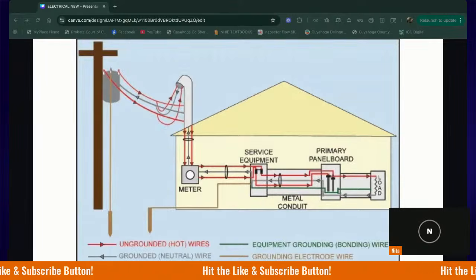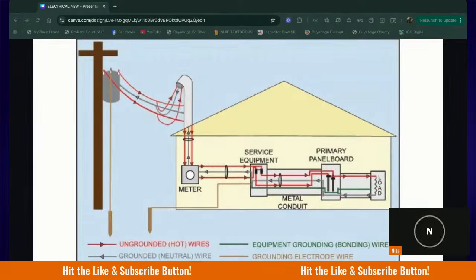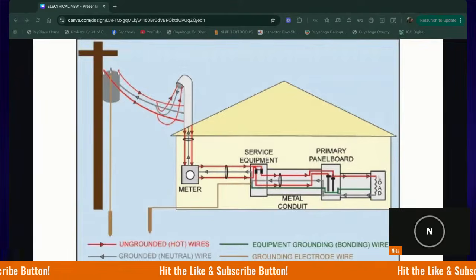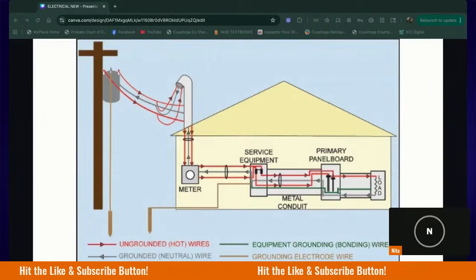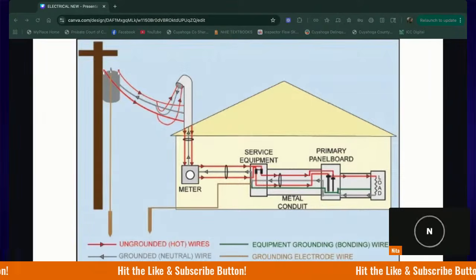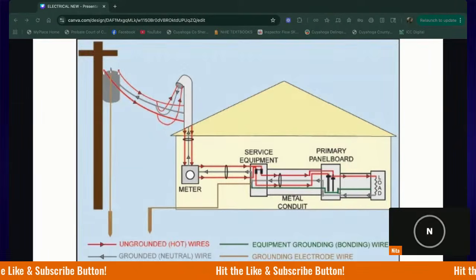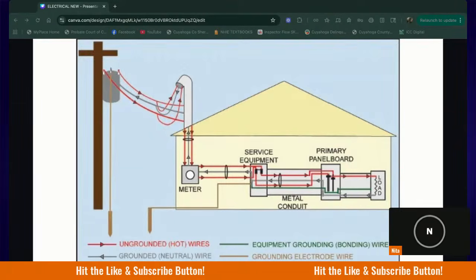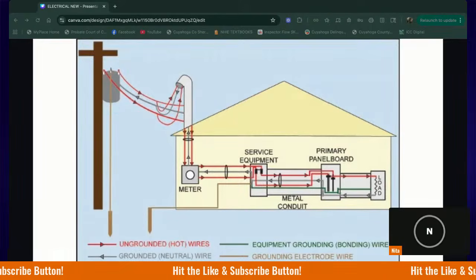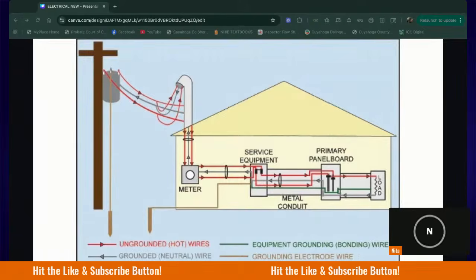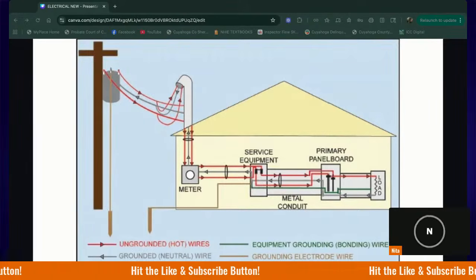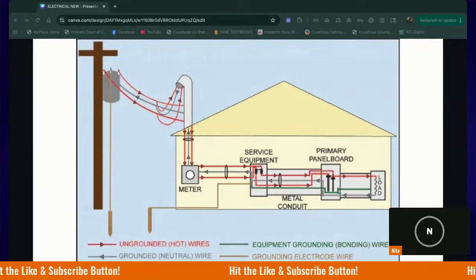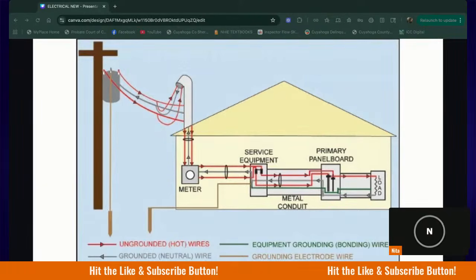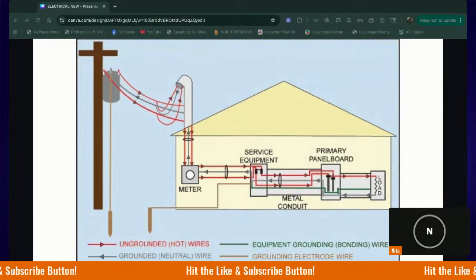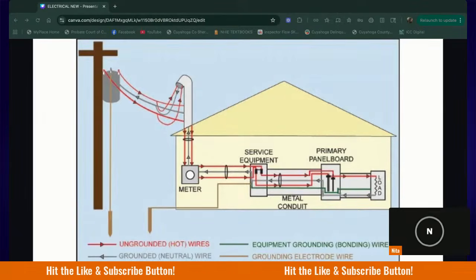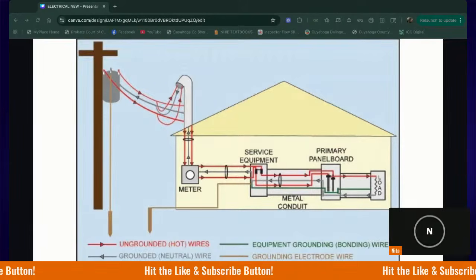Each load or each thing that we are trying to power has what's called an equipment grounding conductor or an EGC. This is the safety wire. Okay, so it is not intended to carry current. When everything is working correctly, this green wire here is not intended to carry current. Its purpose is to create a path if there was a fault. So if something goes wrong in the electrical system and the current goes haywire, a short circuit or something like that, the EGC, our whole grounding system, but specifically this EGC, it is trying to give a path for that current back to its source.